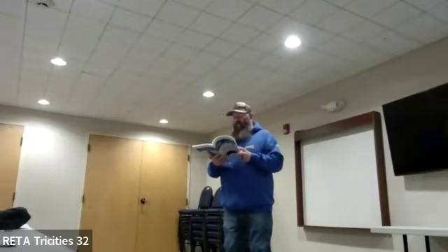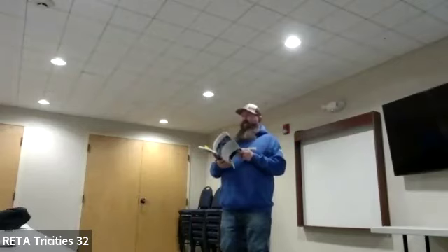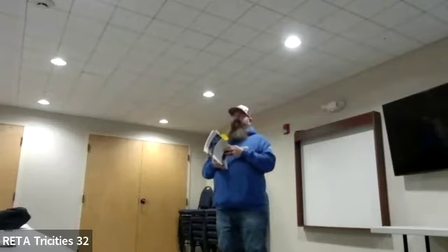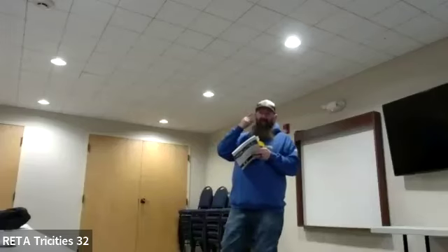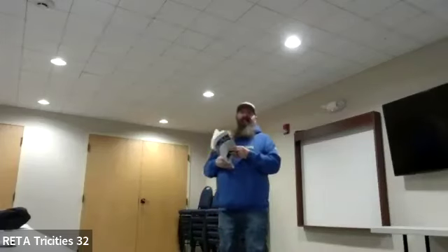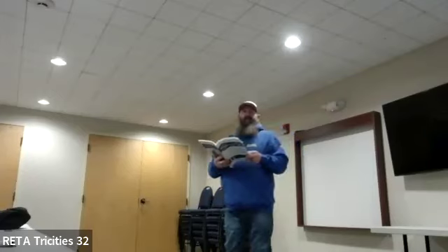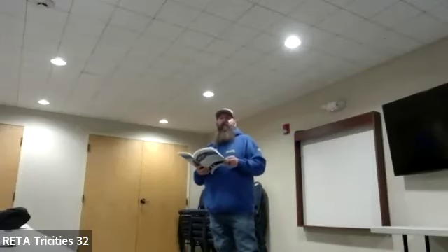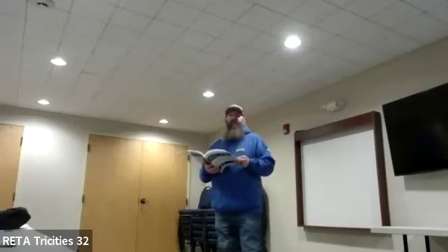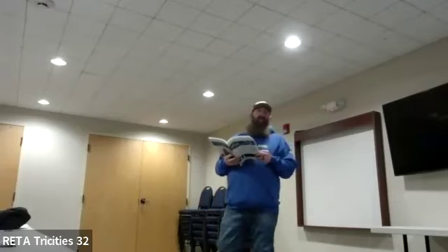Fan belts, they threw in fan belts and we were all discussing this. They say it's replaced every 5 years or where applicable. I feel our OEM gives us good guidance, and if your ears and nose start smelling burnt rubber. Is that just any kind of fan belts, exhaust fans? Yeah, I think condensers anymore, a lot of the bigger ones in the enclosed motors, the green ones, they're direct drive anyway, so.